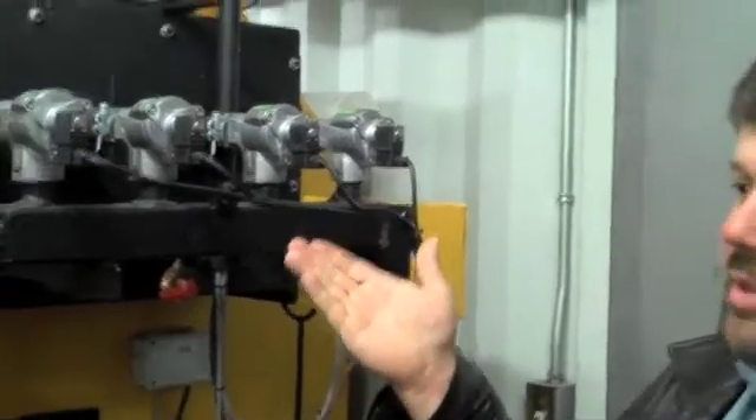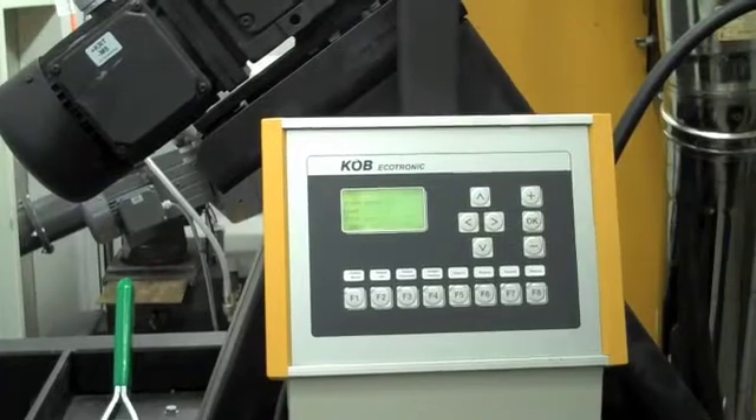There's tube cleaning that keeps the boiler efficient. This is the automatic tube cleaning here — every 500 seconds it'll blow some air into the boiler, keeps the tubes clean. Does that reduce maintenance? We still have to, after so many hours — maybe a thousand hours — go in and clean them manually. I cleaned it once and we got 1,700 hours and it's still running very efficiently. You can also adjust the moving grates and the feed speed for different pellets. We can burn chips or pellets with it.